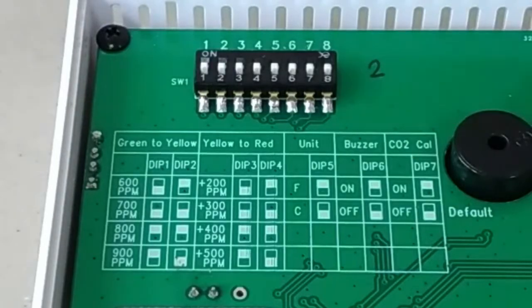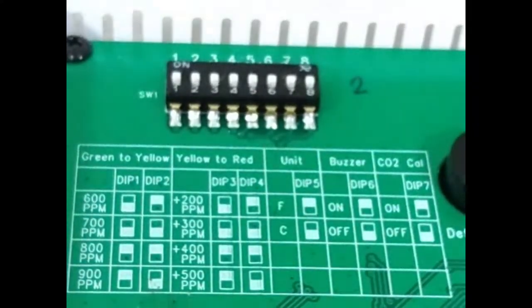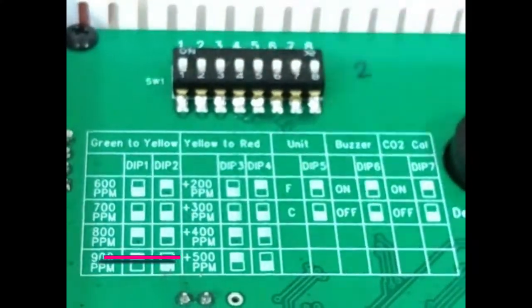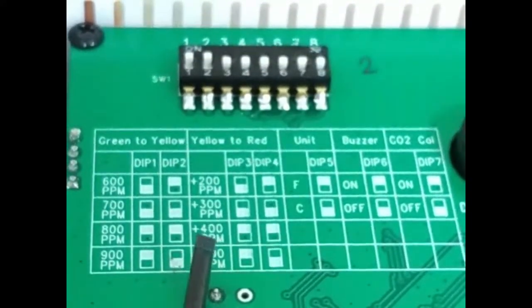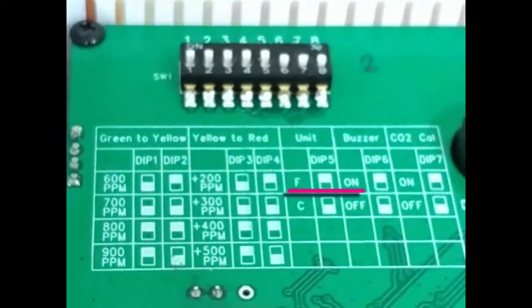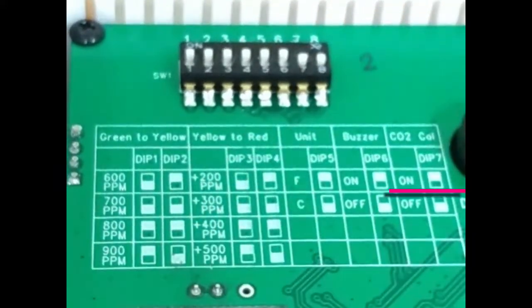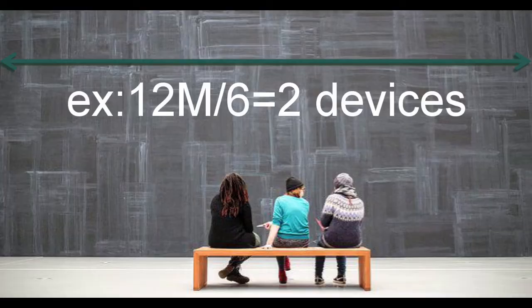To change the setting, use a flat screwdriver to adjust the dip switch. For example, here we show you how to change the yellow threshold to 800 ppm, red threshold to 1200 ppm, temperature to degree F and buzzer to on. The required number of CO2 meters depends upon several factors. However, as a basic rule, you can use the length of the longest wall in the room divided by 6 to get an estimate.